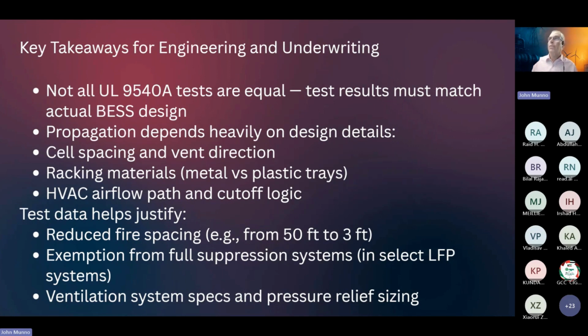And when it's on top, that prevents the exhaust gas or heat from impinging on a nearby module. But it's also subject to snow loads. So you have to be careful that if you are in a snow heavy region, you wouldn't want to put your vent on top. If you are not, then it's okay to put it on top. Then you prevent the vented gases and vented explosion from impacting another module. And we've got to look at the HVAC airflow and the path and how we cut it off, because that will influence these fire tests as well.